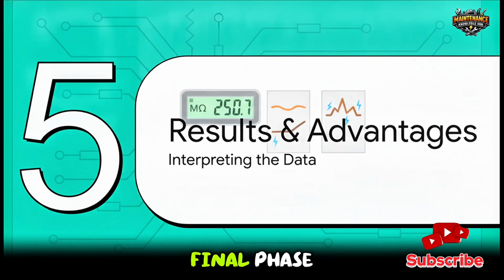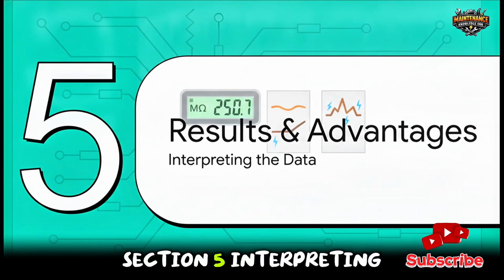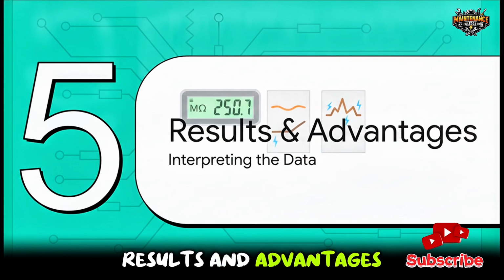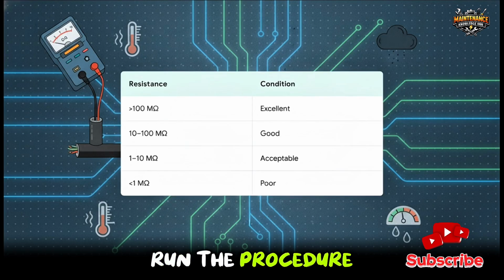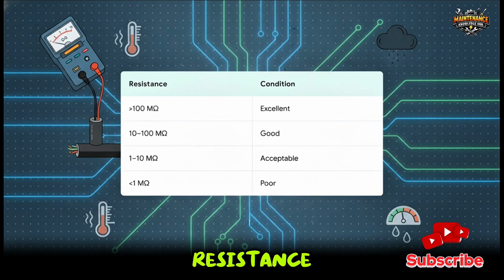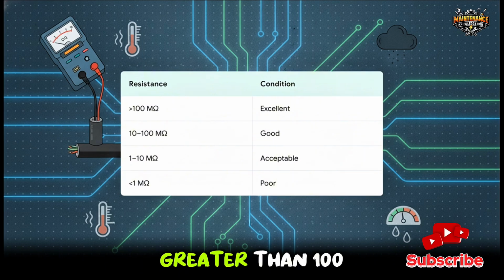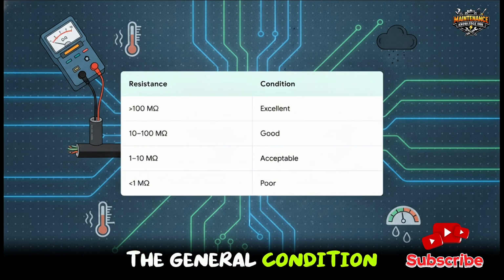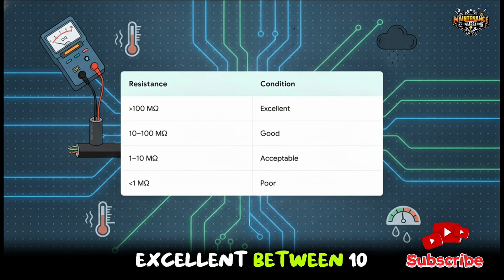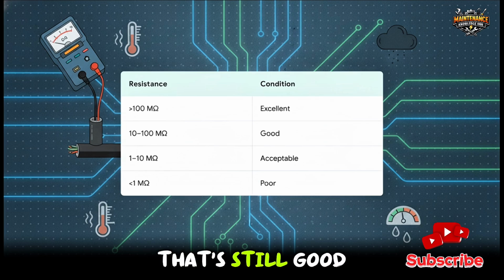Moving into our final phase, Section 5, interpreting results and advantages. So, you've safely run the procedure, and now you're staring at a resistance number on the screen. Translating that data is actually pretty straightforward. If your insulation resistance reading is greater than 100 megaohms, the general condition of your equipment is considered excellent. Between 10 and 100 megaohms, that's still good.